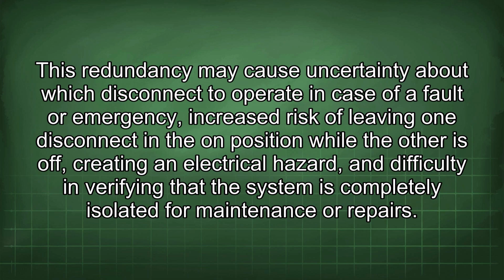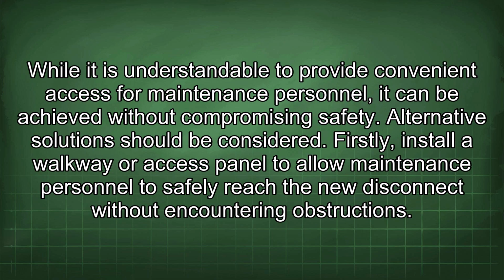This redundancy may cause uncertainty about which disconnect to operate in case of a fault or emergency, increased risk of leaving one disconnect in the on position while the other is off, creating an electrical hazard, and difficulty in verifying that the system is completely isolated for maintenance or repairs. While it is understandable to provide convenient access for maintenance personnel, it can be achieved without compromising safety. Alternative solutions should be considered.